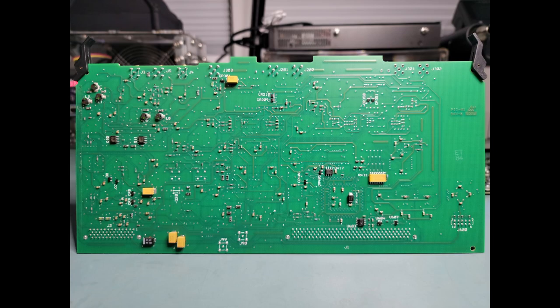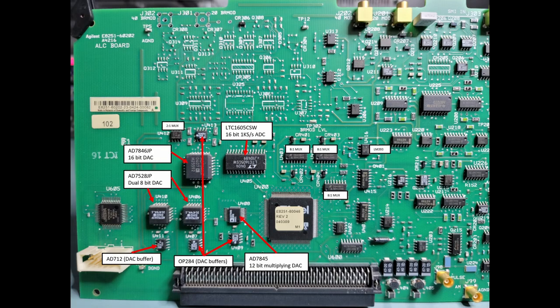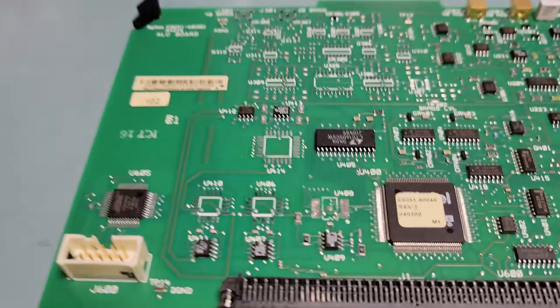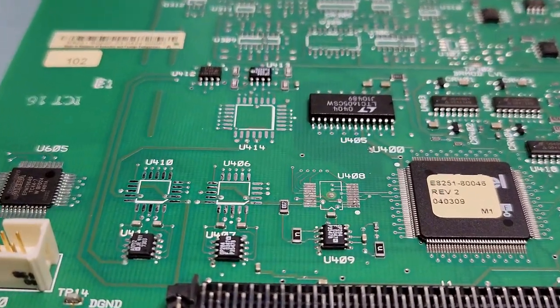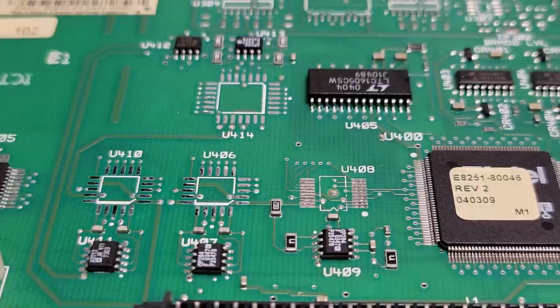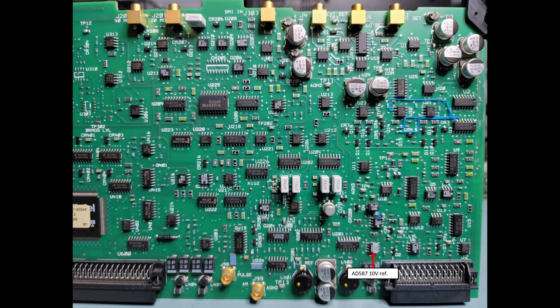Because I'm not able to really probe this board easily, I decided to go with a sort of shotgun replacement method. So these are the majority of the parts I went ahead and replaced on the ALC outright. We have, of course, the main ADC, which is that LTC part. And then we have a couple of DACs surrounding that and op amps that are buffering the DACs, and a couple of other parts as well, just for good measure. The only other part that I ended up replacing in addition to those was the high stability 10 volt reference that was on the other side of the board.